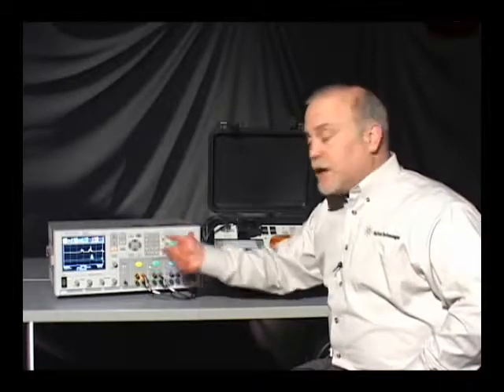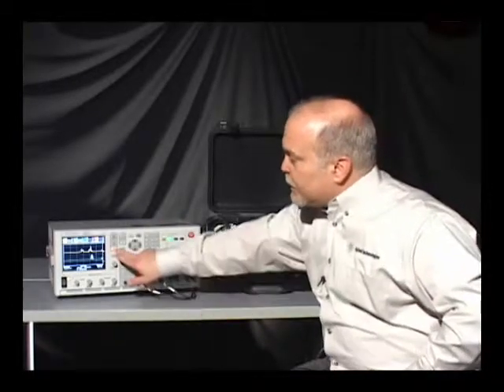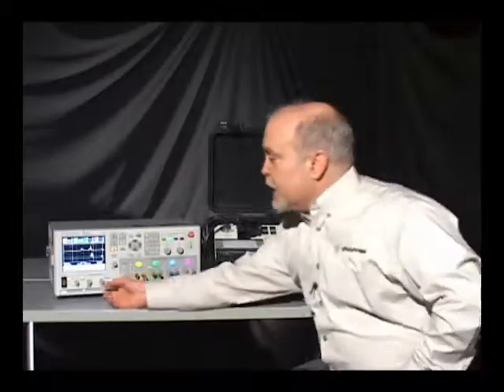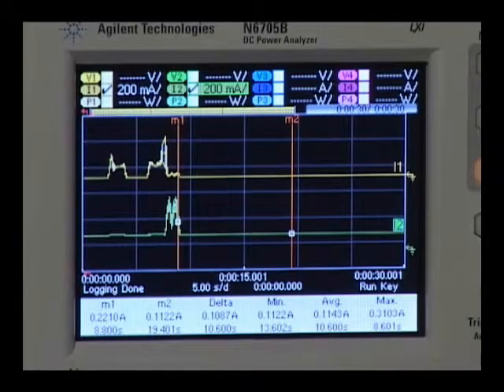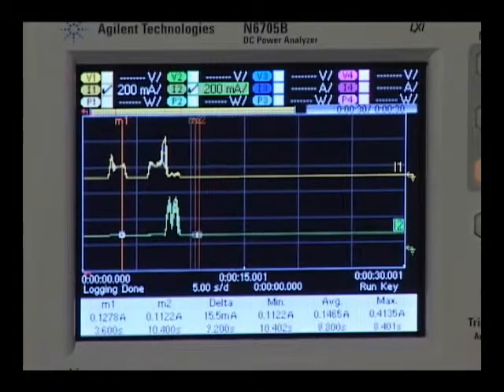Or I can interact with it directly on the screen of the instrument by pushing the data logger button again. I get some markers. And I can go ahead and use the markers and take measurements off of the data logger.